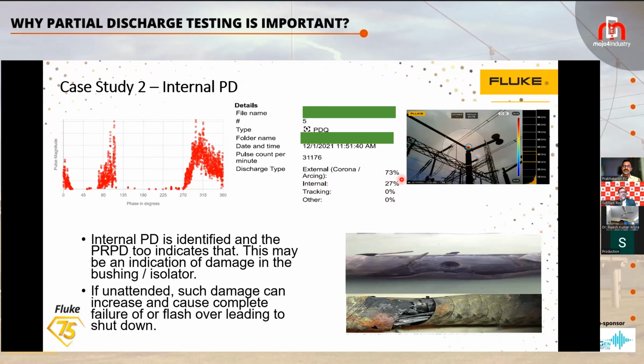And how this can help: most of the time, whenever we go to a utility company, people say that because of partial discharge, we never face a problem. But they don't know what exactly is happening. Maybe the failures are categorized as a different failure. That may be the reason. And here, if you are not doing this on a periodic basis, this can go up and can fail the entire system, and this can create more damages. The internal failures can create damages in cables and various other things. I have not put many examples here, but many of you will be aware of those kinds of situations.